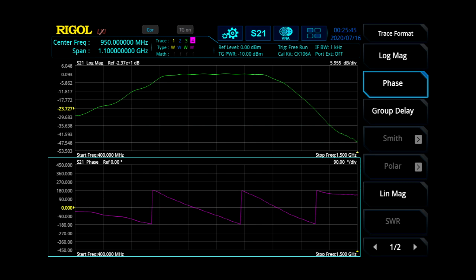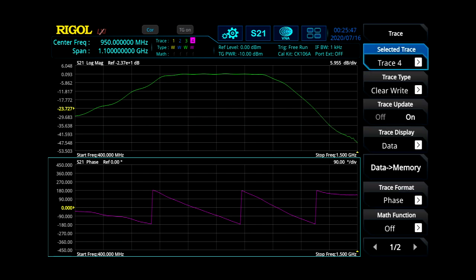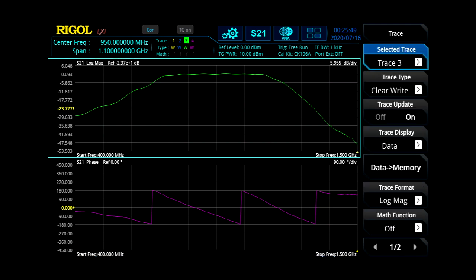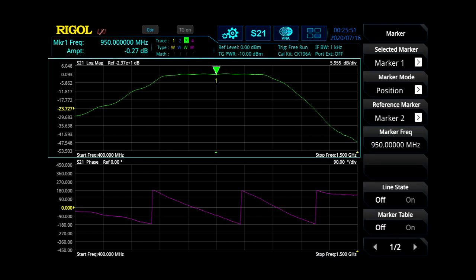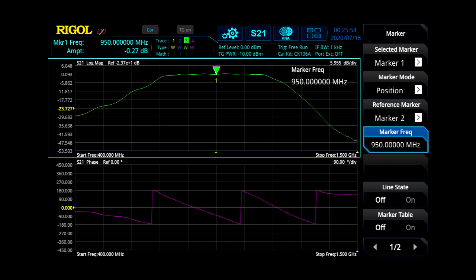The other thing we can do is go into our marker menu. Within the marker menu, we can move our marker to find the specific edges of our filter or cabling, to determine frequency ranges of interest or hard edges. We can also use this same technique on our lower trace to find when the phase changes.